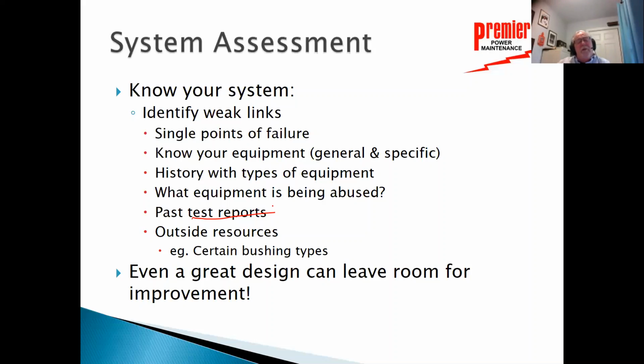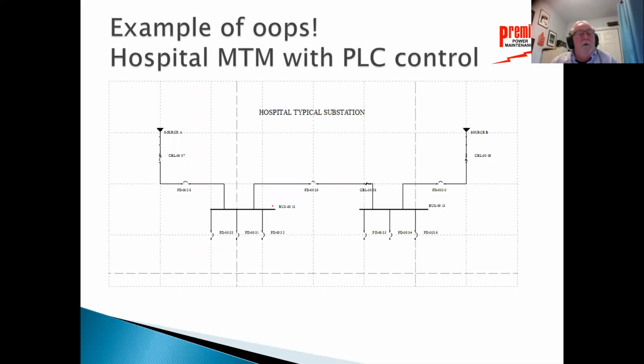We need to go to outside resources. For instance, certain bushing types, years ago, like the GE type U bushing, everyone in the industry knew that there was a problem with those bushings, and most utilities went through the process of replacing those bushings before they had a failure. My company was doing that as well, and unfortunately there was one transformer we were about 2 weeks short on getting it replaced before it failed, and we lost the transformer. So staying in touch with the outside resources, the community that we have, to understand what downfalls certain pieces of equipment have. And we always need to understand that even if we have a great design, it can still leave room for improvement. So I've got some examples.